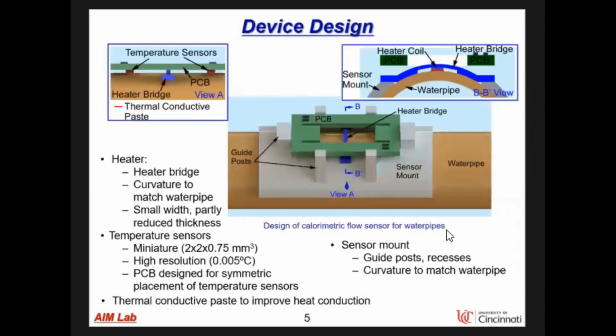So this is the design of our calorimetric flow sensor. It consists of a heater bridge, a printed circuit board, and a sensor mount. As shown in the cross-sectional view BB dash, the heater bridge follows the curvature of the water pipe with a protrusion in the center for integration of the heater coil. The bridge has small width and is partly reduced in thickness to minimize the heat loss along the bridge.